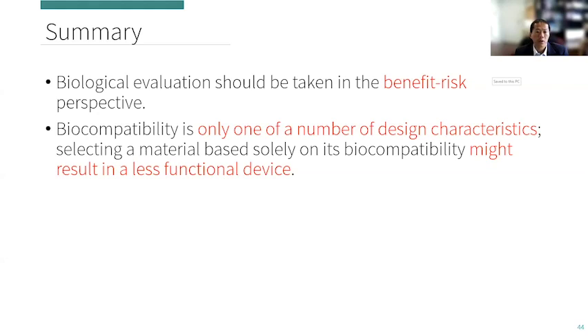And I think it's important that the FDA also recognizes, and they call this out in their guidance, that biocompatibility is only one of a number of design characteristics, and they caution about selecting a material based solely on its biocompatibility because it might result in a less functional device.